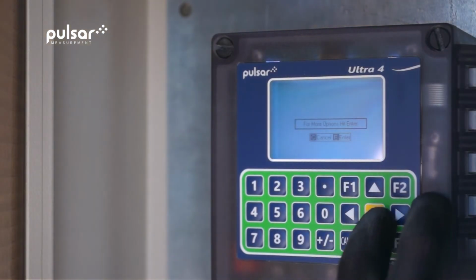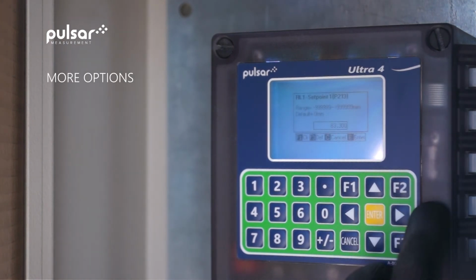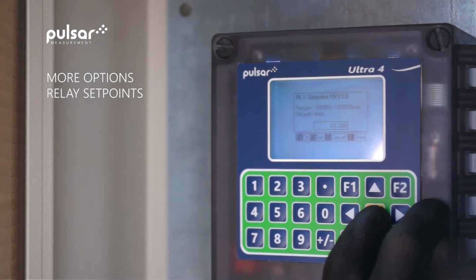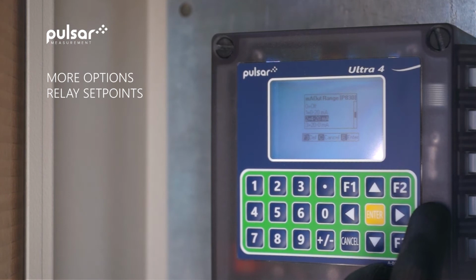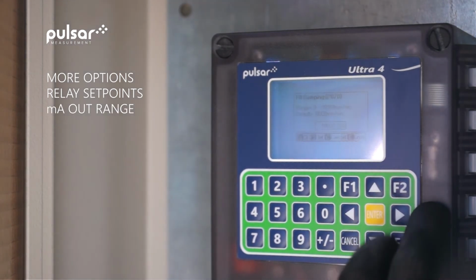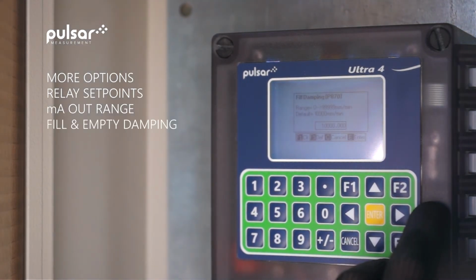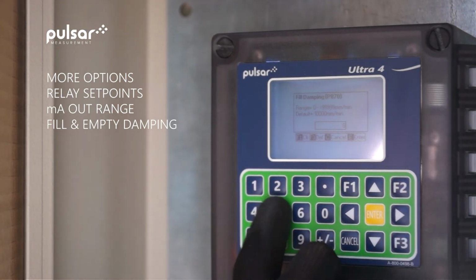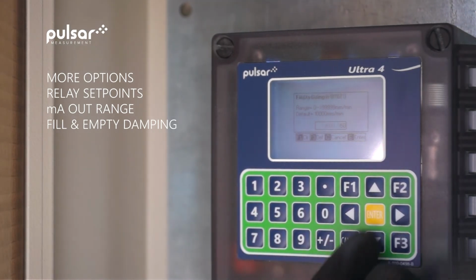We can press enter to have some more options. Here we can choose to change our relay set points if we want. I'm happy with what they are at the moment. We can adjust our milliamp output range, but we can also adjust our fill and empty damping. So we can set this to 50 millimeters a minute. This is more suitable for our application.